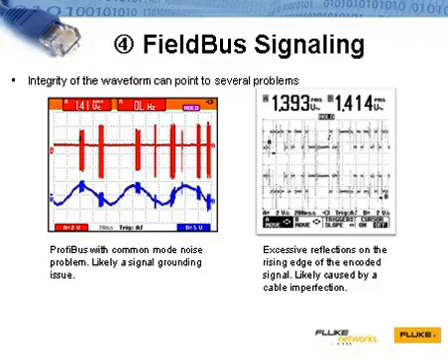The first example on the left-hand side shows a Profibus network where one of the devices connected on the network was not properly grounded. This created a common mode signal on the digital line. The second example on the right-hand side shows the impact of an impedance mismatch in the transmission path. An impedance mismatch can create a reflection in the waveform. Excessively high or long duration of reflections can potentially confuse the receiver to misinterpret a logical 1 or 0.